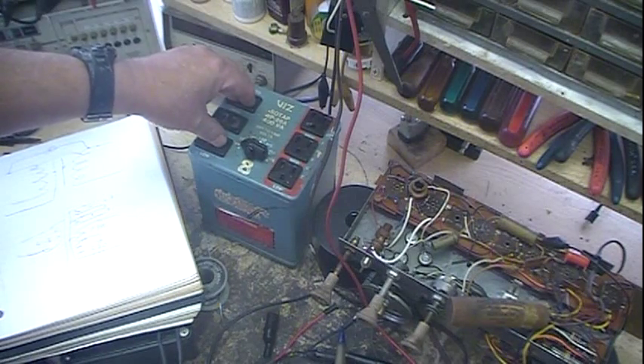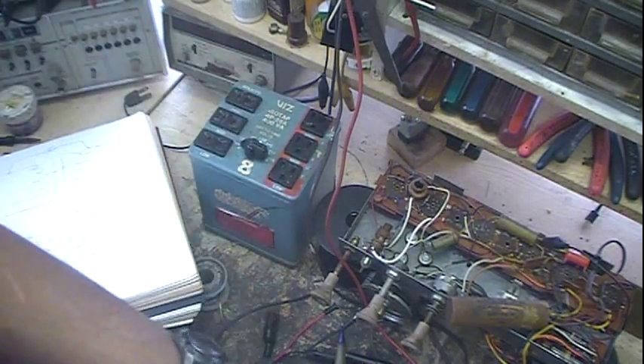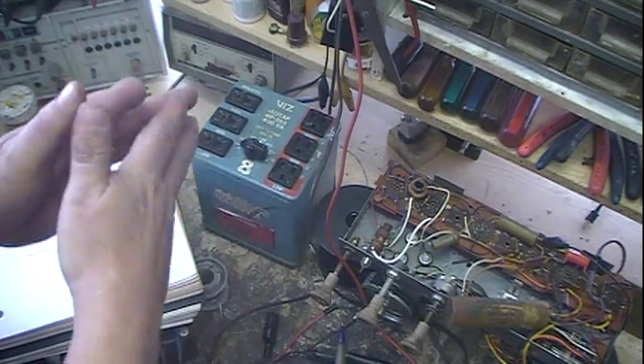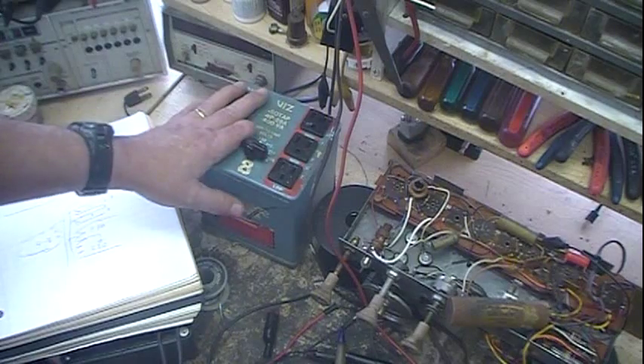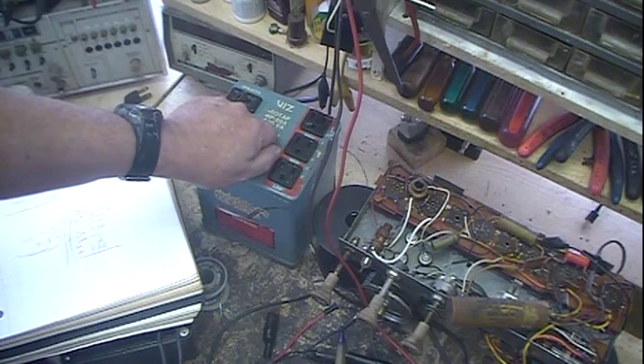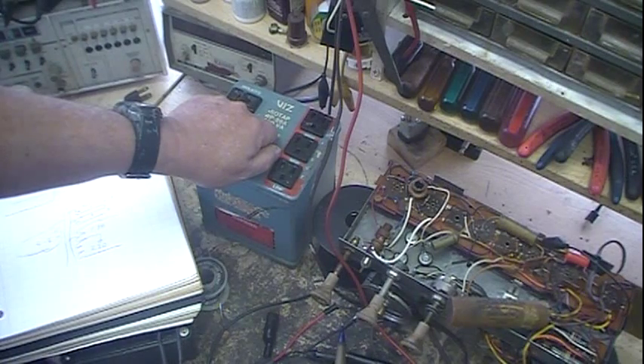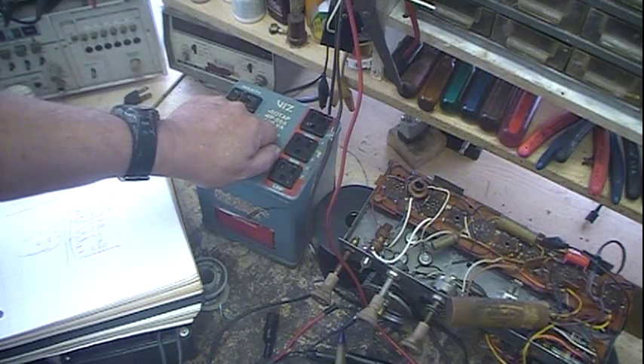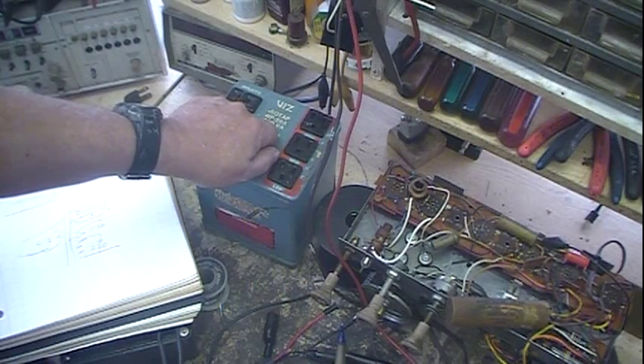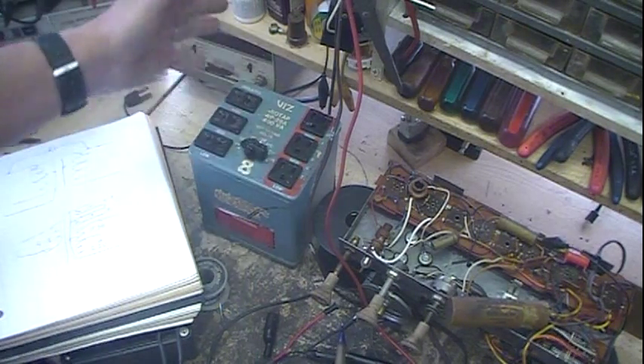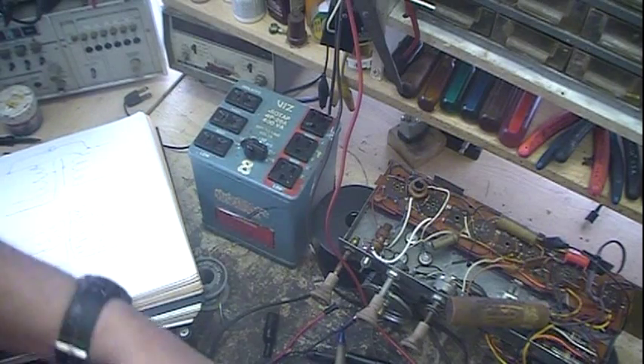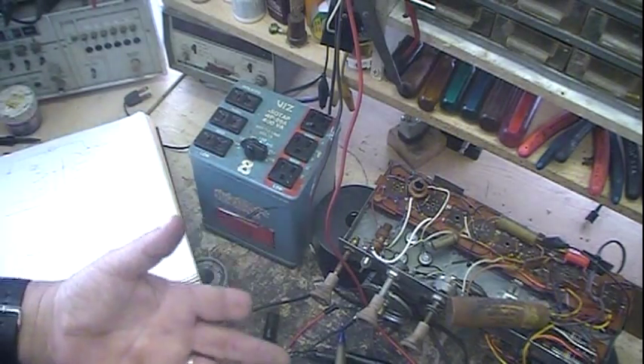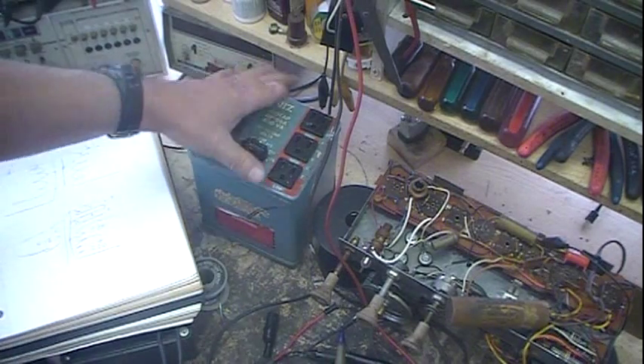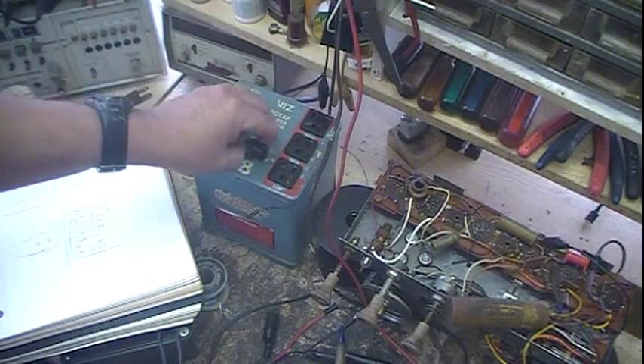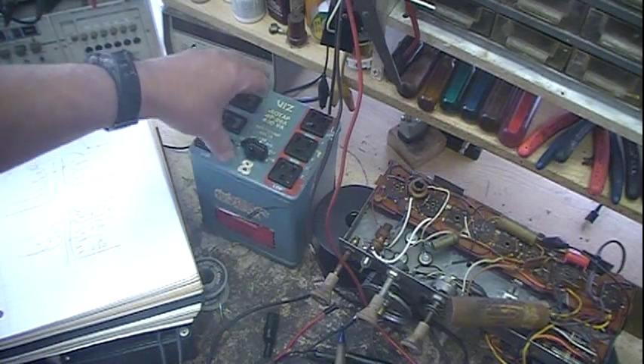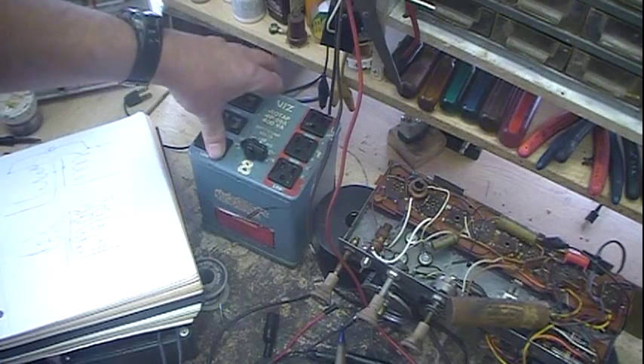Use the ohmage, and it should be completely out of limits. Where this was showing OL, out of limits, there's nothing there. So if you're reading any resistance, a few hundred ohms, a few tens of ohms, or even 0 ohms, or 1 or 2 or 5 or whatever, anything other than out of limit, or whatever your meter displays when the resistance is too high for it to check, it's basically fully open, there's nothing there. Whatever it reads, that's what you should be reading.